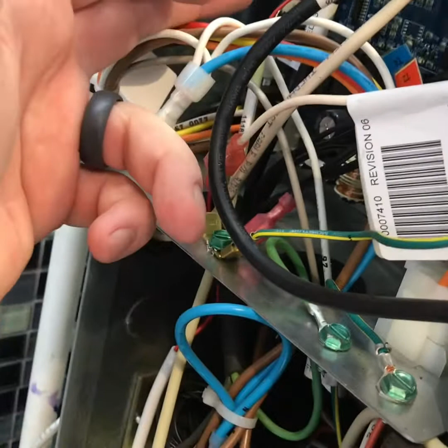On this particular model, you can use the red and black wire, and of course this is where the condensing unit is up on the roof. A line set runs up through the wall and out, and yeah, so we will order one of those. I'll replace it. We'll test this thing again and watch it make a batch of ice, watch it go into a harvest, watch it fall off, and make sure everything is working the way it ought to.